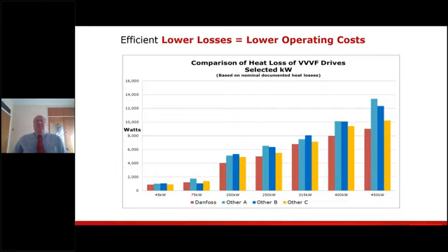So, for example, the Danfoss drive incorporates a built-in DC link choke harmonic filter and RFI filter. And it can be installed with at least 150 meters of screened motor cable between the drive and the actual motor as a standard. And any losses in the drive associated with these filters are actually included in our stated efficiency rating of 98%. Now, manufacturers who offer these filters as options and need to fit additional filters for 150 meter motor cables may not include these in their standard efficiency ratings of 98%.